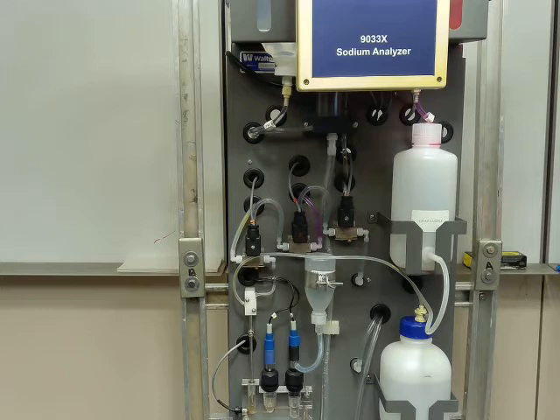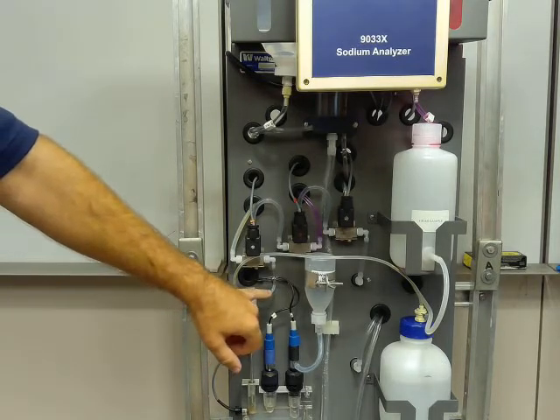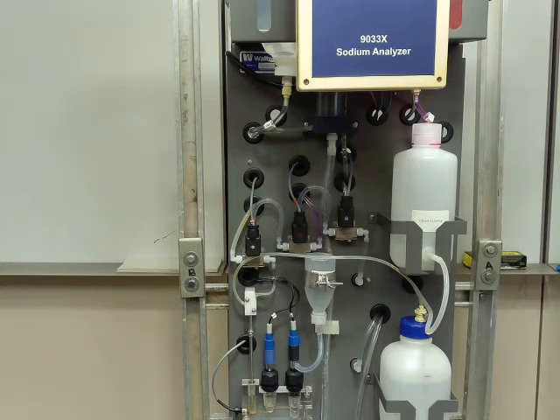But also, if there is a problem with flow, a blockage in the tubing or something like that, you'll see it at the flow cell with this bubbling will slow down. You won't see much sample going through there. And again, the biggest chance for a blockage would just be in this piece of tubing here into our entrainment, just by the nature of it being the thinnest piece of tubing on the system. Again, most times with pretty ultra pure water, that's not too much of an issue, but every once in a while you get some debris that can come through and get stuck and needs to be flushed out.